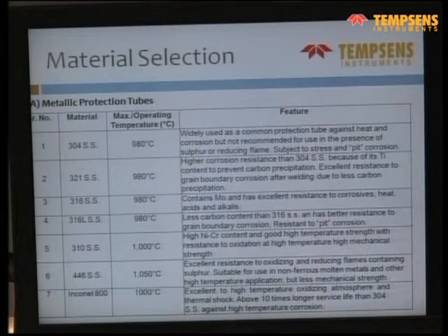For example, 446 and 310 both have a similar temperature range, and even Inconel 800, you can see it is about 1000, 1050, or again 1000 degrees centigrade. But 446 is more used, it has better life in a sulfuric atmosphere, or in the case of a non-ferrous molten metal. So 446 is a chosen material in a cement plant or a molten aluminum plant, or primary aluminum plant, where they want to take the temperature of molten aluminum. So according to the chemical as well as the temperature, you have to choose the right material of the thermowell.